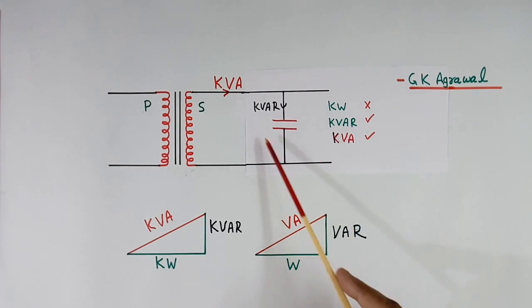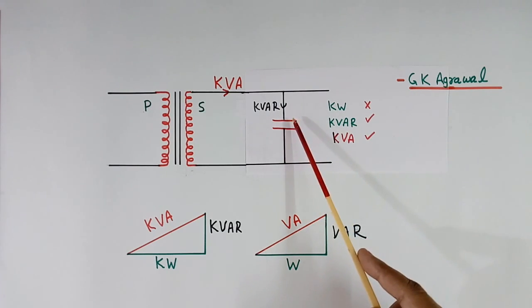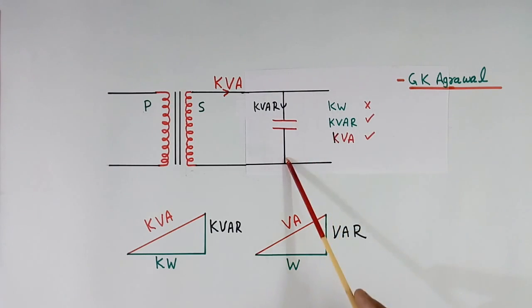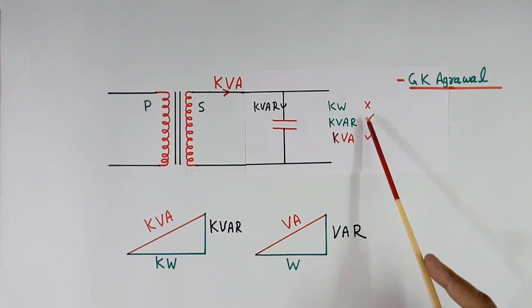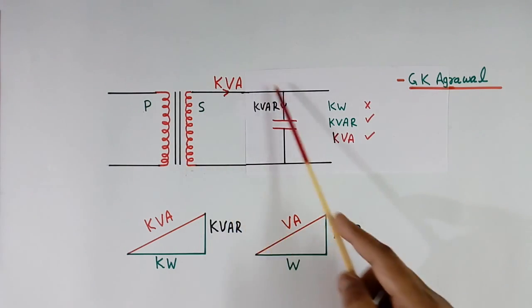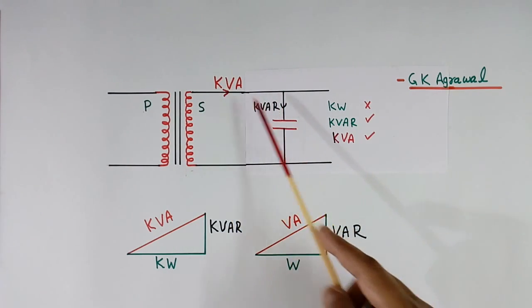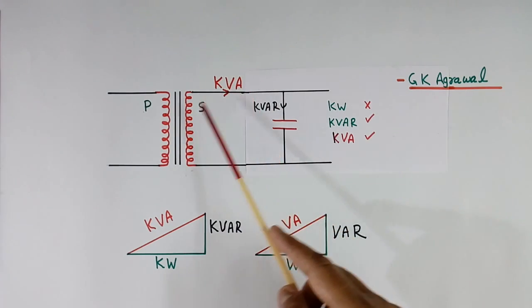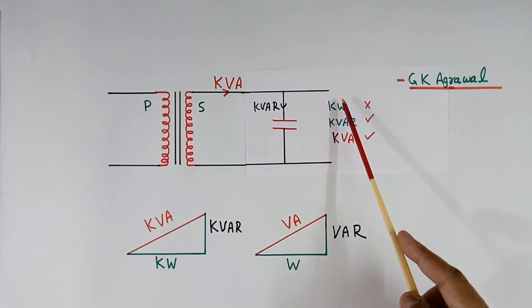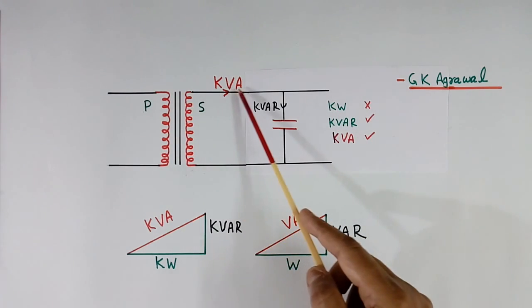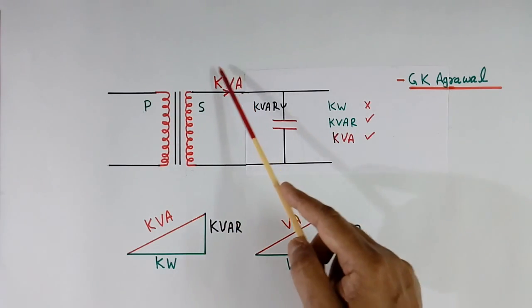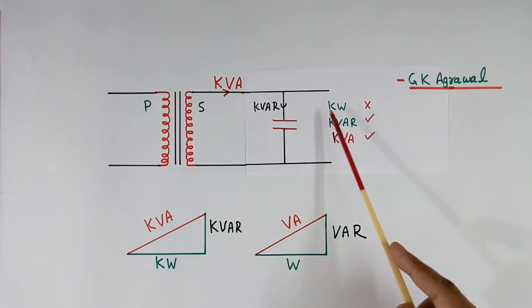Here I have connected only one capacitive load — no resistive load. So kW is not there, only reactive power kVAR is flowing. The same power will flow in the transformer as well, so kVA and kVAR will be equal here. This kVA power will flow in the transformer. So you see, kW is not there, but kVA power is still flowing — so the transformer is rated for kVA, not in kW.